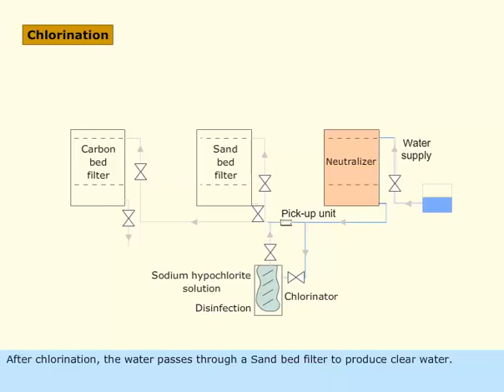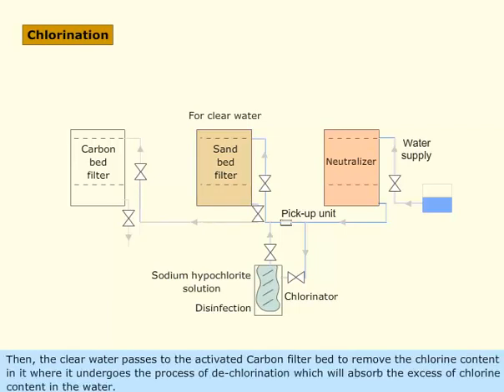After chlorination, the water passes through a sand bed filter to produce clear water. Then the clear water passes to the activated carbon filter bed to remove the chlorine content in it, where it undergoes the process of dechlorination, which absorbs the excess chlorine content in the water.